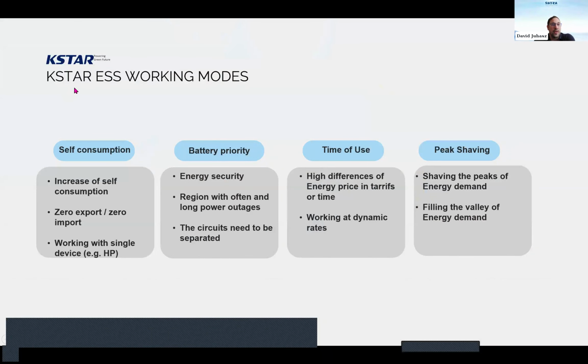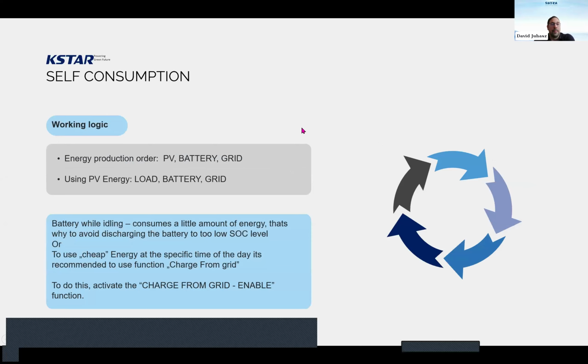Okay, regarding the working modes, there is self-consumption, where the extra PV goes to the battery packs, or if the battery packs are full, we can feed out. There is battery priority, where the storage can only discharge when there is no AC; the time of use settings; and peak shaving, for shaving the peaks of the energy and filling the valleys of the energy demand. The working logic of self-consumption has an energy production order. When the PV produces energy, it goes to the battery, then to the grid. For using this PV energy, it goes to the load first, then the battery, then to the grid.